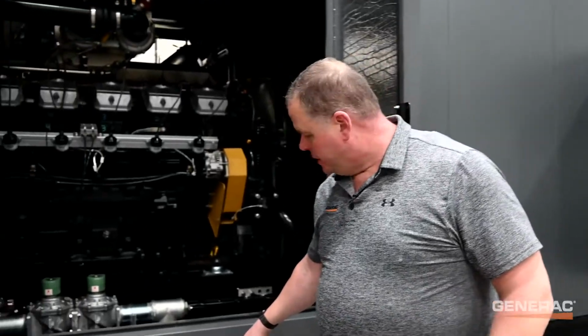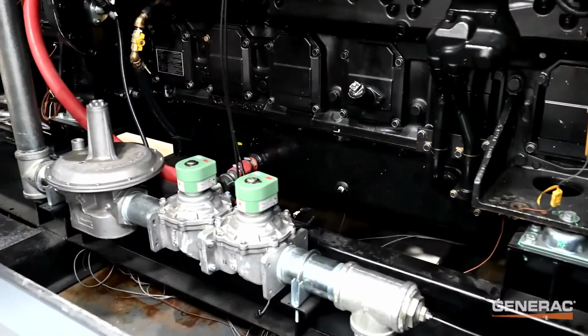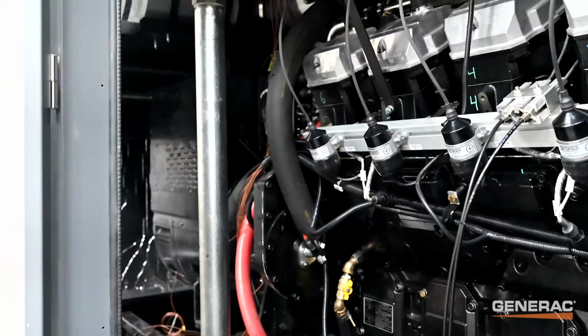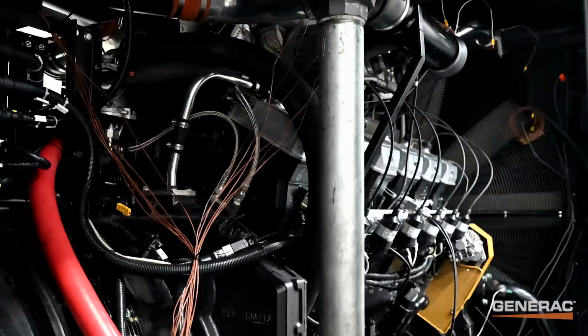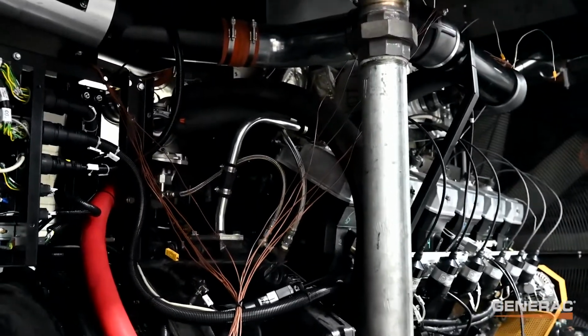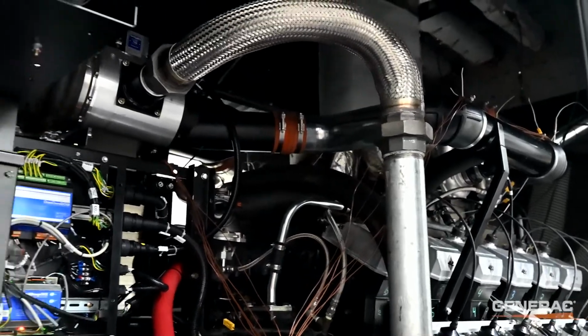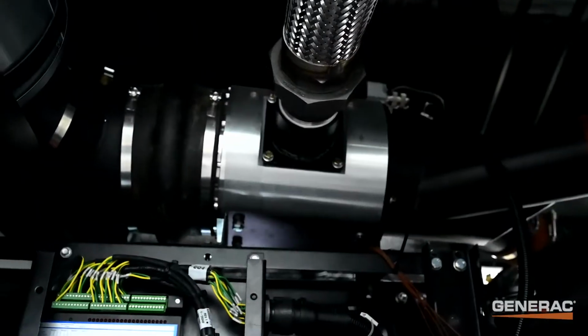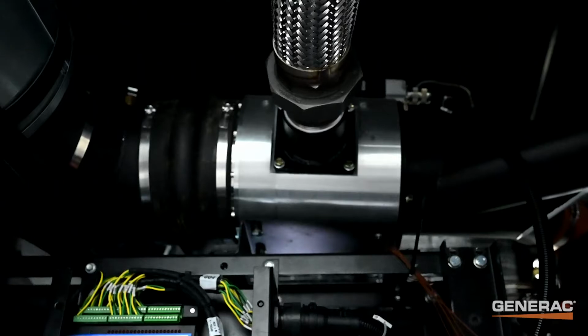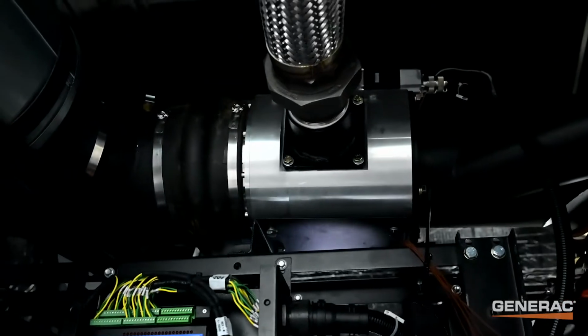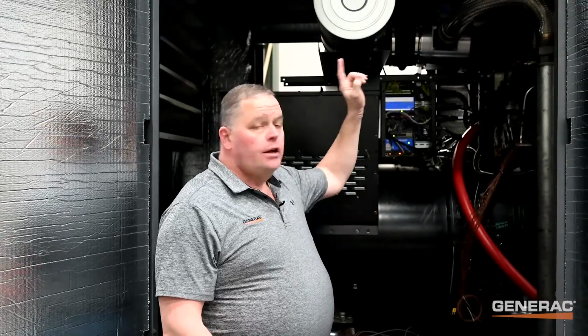Now I'd like to take you through our fuel system. We have some very innovative things going on in our fuel system here. Natural gas comes into the generator set down here, comes into our fuel system with shutoff valves and regulator, and we constantly monitor the incoming fuel pressure. We bring that through piping up to our mixer. This is our VeraFuel mixer that takes the incoming gas, mixes it with the air to get the ideal mixture of air fuel going into the 4 turbochargers that Todd told you about earlier.